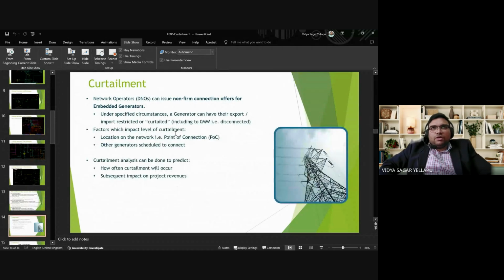So, whenever a generator is to be connected to the network, because of these reinforcement limitations, as they have to use the existing network, the network operator issues non-firm connection offers to the generators. That means that the generator, if there are no constraints, can export the power, and if there are constraints, it cannot export the power. It has to limit its export. That is the concept of non-firm connection. Under specified circumstances, a generator can have its export or import restricted or curtailed. That means it can even be curtailed to 0 megawatts.